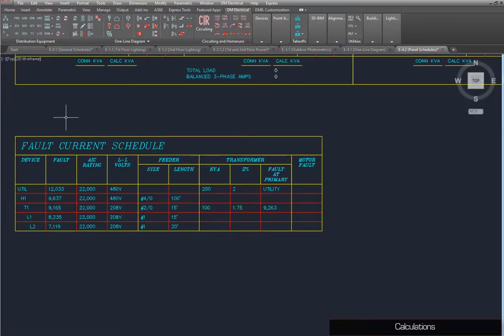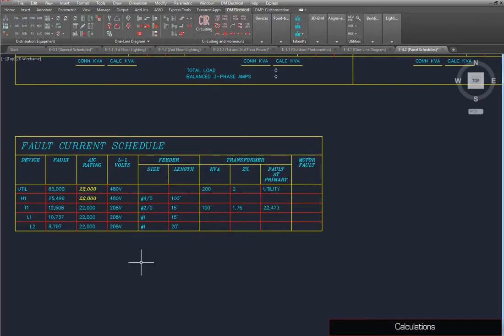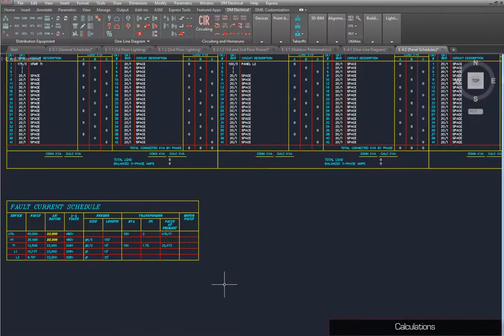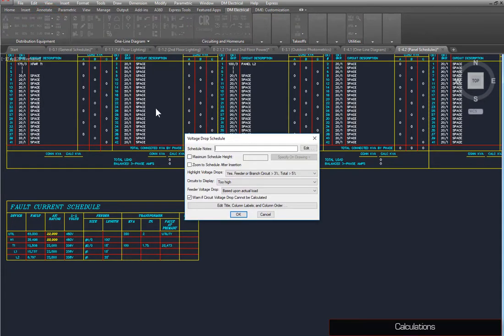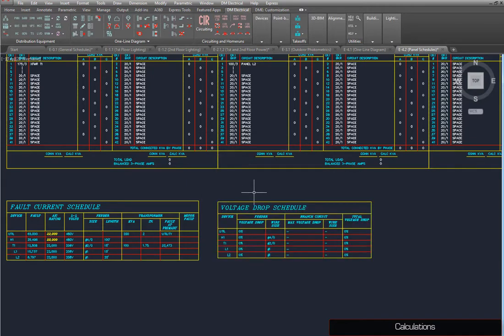Run the Insert Fault Schedule command again, to see how the values change. To perform voltage drop calculations, run the Insert Voltage Drop Schedule command. As with the Fault Schedule dialog box, you can use this to set what information is displayed in the voltage drop schedule. For now, we'll use the default settings. Press the OK button to insert the schedule on the drawing. Because no loads have been defined on the distribution equipment, the voltage drop is calculated as zero.